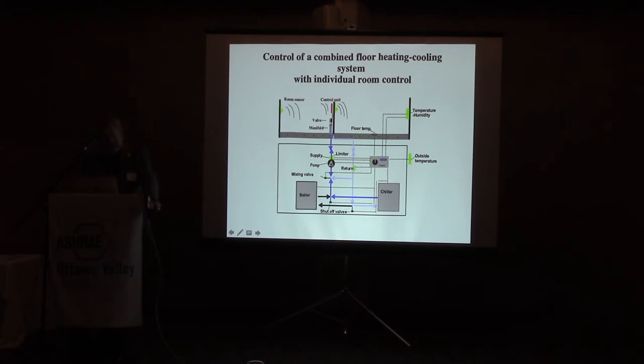And then in each room, it is required in European countries that each room has its own thermostat, both for reducing energy use but also for comfort. So normally now we have wireless sensors: a room sensor sends the signal to a valve, and when we don't need any more heating, it closes the valve. And that's normally how the heating is controlled.